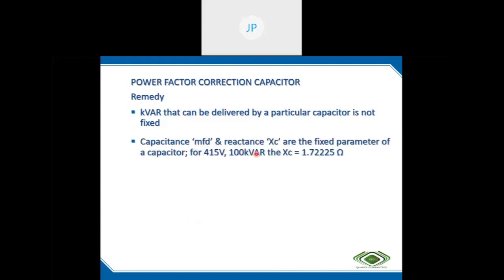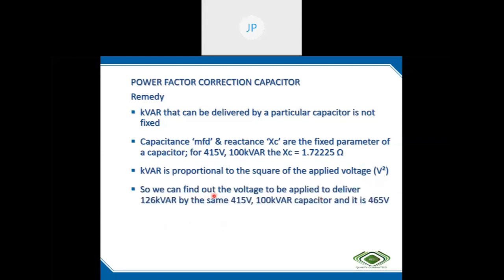The kVAr delivered by a capacitor is not fixed. Its capacitance and reactance are the fixed parameters. For 100 kVAr at 415 volt, the Xc is equal to 1.72225 ohms. This will not vary, and the MFD will not vary. But kVAr is proportional to the square of the applied voltage. That means if we connect a 100 kVAr capacitor rated for 480 volt or 550 volt, for more safety, we never get 100 kVAr. You may get only 60 or 70 kVAr. So we can find out the voltage required to deliver 126 kVAr from the same 415 volt 100 kVAr capacitor, and it is 465.